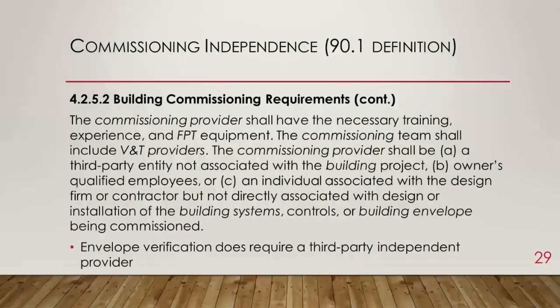And then as far as commissioning independence, we go to a middle ground: the individual doing either functional testing or commissioning could be associated with the design firm or contractor, but not directly associated with the design or installation of the building systems, controls, or envelope being commissioned. So again, you have to have that internal firewall with the individuals doing that work. Although, envelope verification does require a third-party provider.